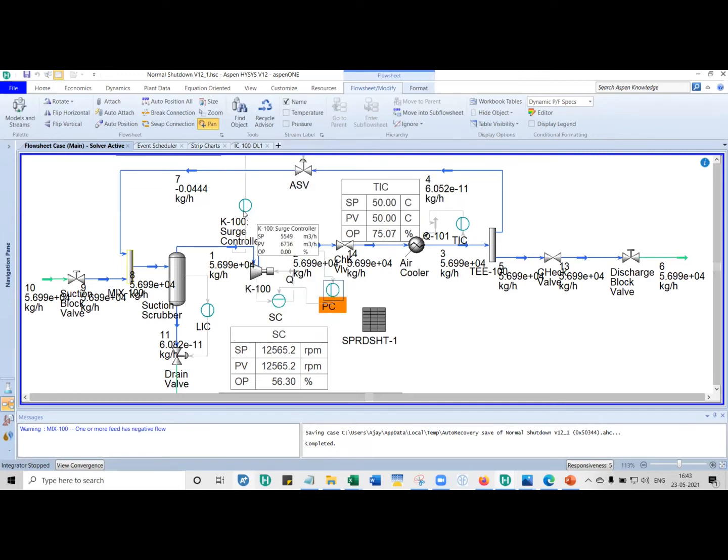If the surge controller is still functioning, then as the compressor is starting to coast down, this controller will try to keep closing the anti-surge valve. We don't want that to happen. So we must disconnect the controller from messing around with the anti-surge valve, and the pressure controller from messing around with the compressor. We don't want any speed control when the compressor is coasting down.